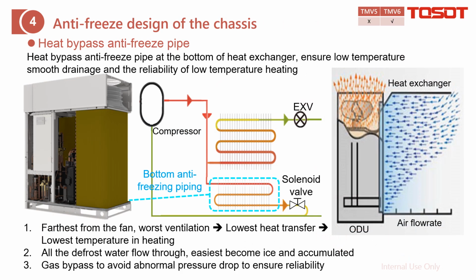Anti-freeze design of the chassis. At the bottom of the outdoor heat exchanger, it is another cycle, which is different from the upper side. First of all, as we know, if this area is far away from the top fan, the ventilation also becomes small, which means the heat exchange rate also becomes very low. On the other hand, during defrost, the water from the ice will accumulate at the bottom, and then it can easily become ice in the next heating cycle.